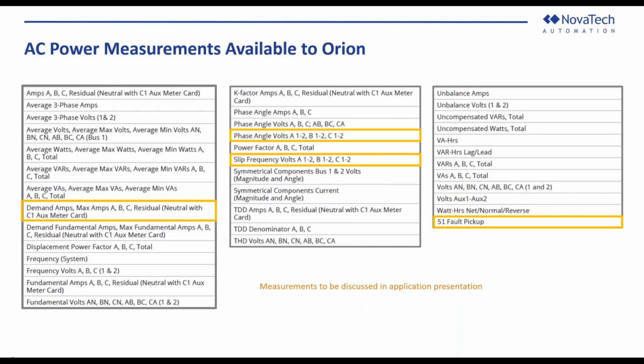The AC power measurements available to the Orion are detailed there. The ones that are highlighted are the ones that we'll talk about a little bit more in the application. The measured quantities, the full scope of amps, volts, watts, vars, frequency, energy, that kind of stuff, plus a few extra things. As you see highlighted there, we have a 51 fault pickup, we got phase angle volts, and the slip frequency volts between A and B, or between lines 1 and 2, or buses 1 and 2. That gives us an idea of whether we can close two sources in on each other, whether they're in sync or not.